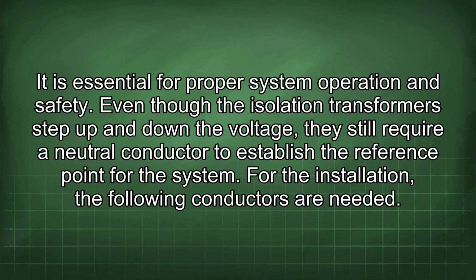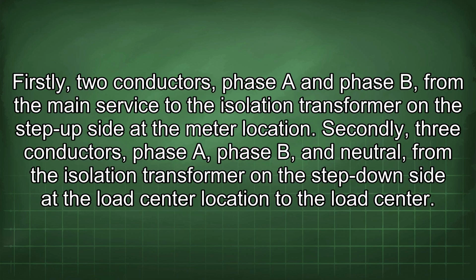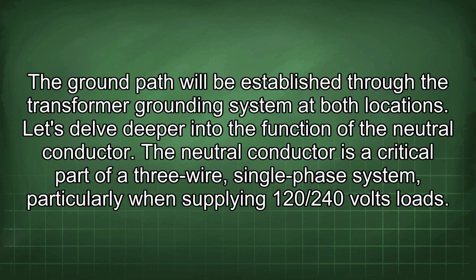For the installation, the following conductors are needed. Firstly, two conductors, phase A and phase B, from the main service to the isolation transformer on the step-up side at the meter location. Secondly, three conductors, phase A, phase B, and neutral, from the isolation transformer on the step-down side at the load center location to the load center. The ground path will be established through the transformer grounding system at both locations.